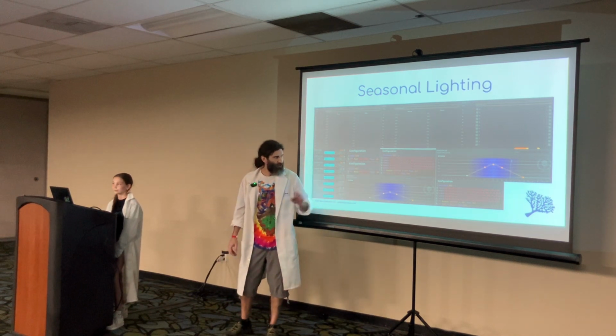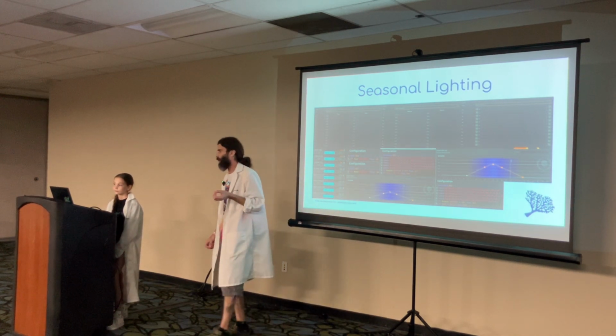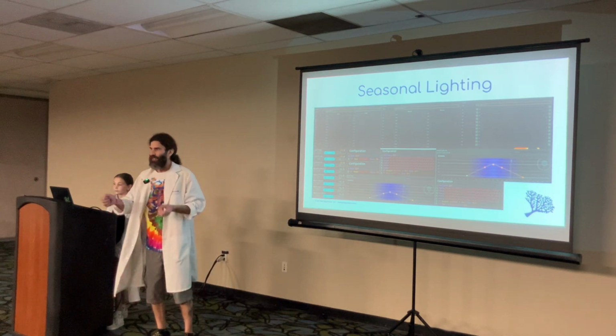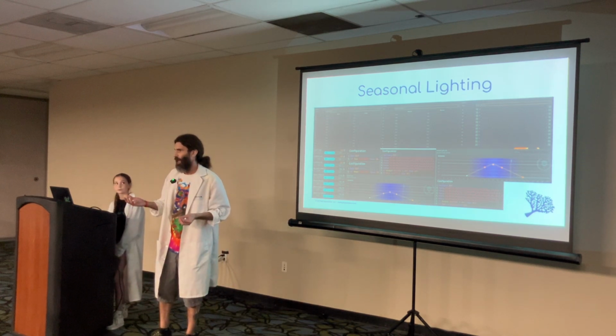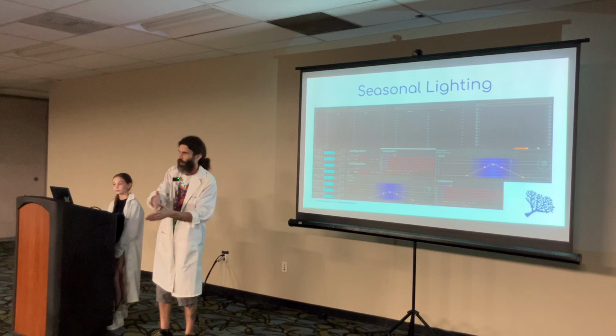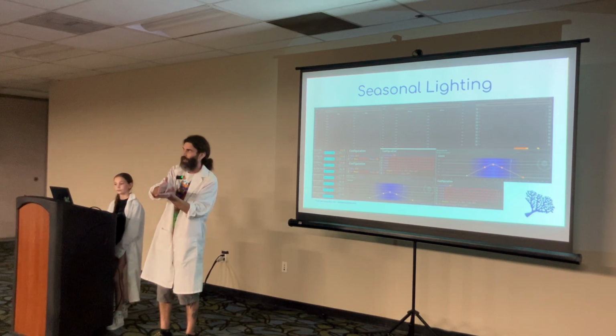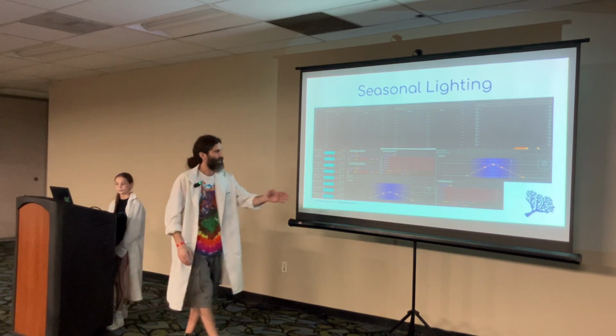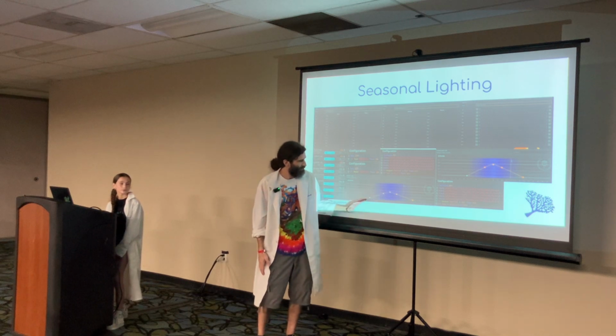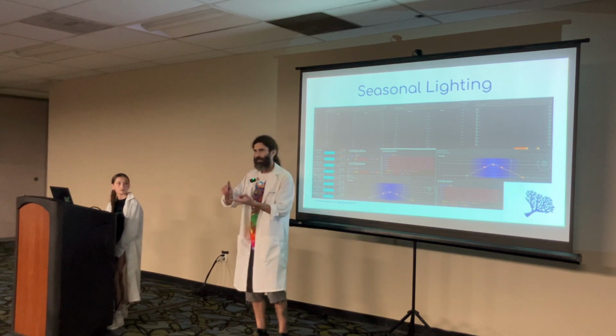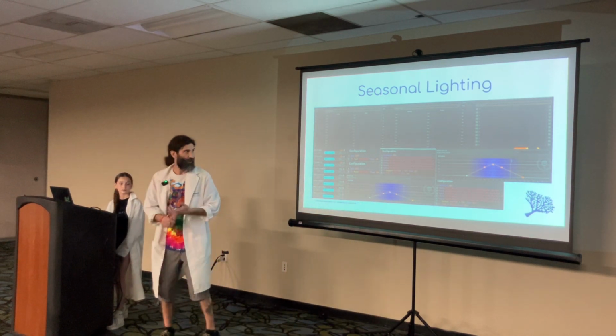They were using oscillations, and I didn't like how that worked, because if you reset the lighting, or say a power outage happens, the oscillation goes back to the start. So your intensity goes back to the starting intensity rather than where you were at that point in time. That's why a table works much better for having a nice gradient of changing intensity and color patterns.